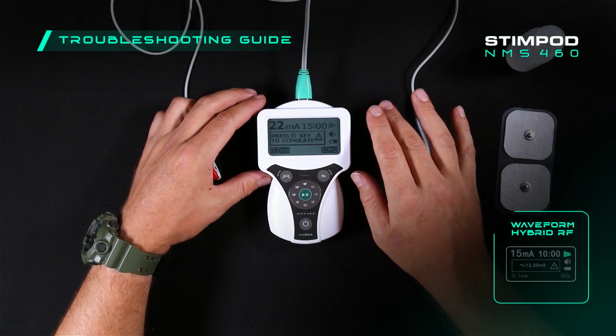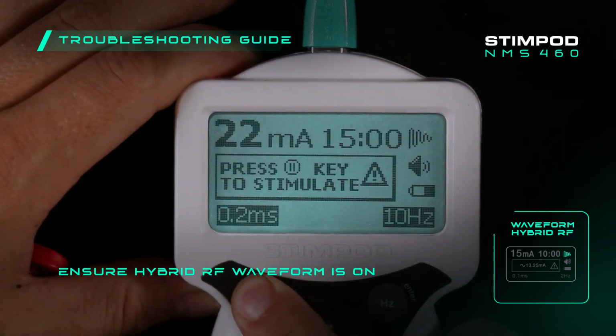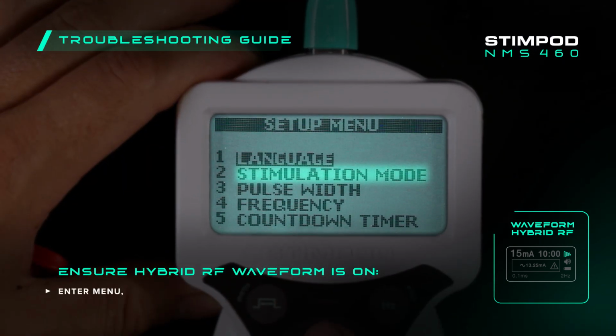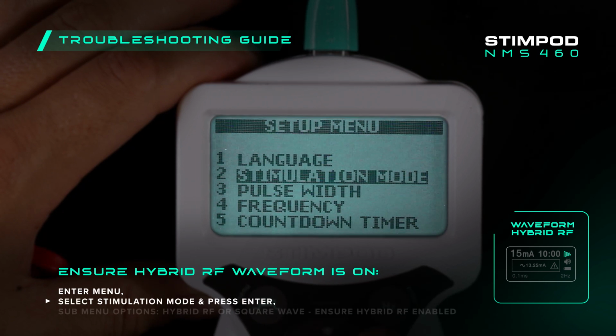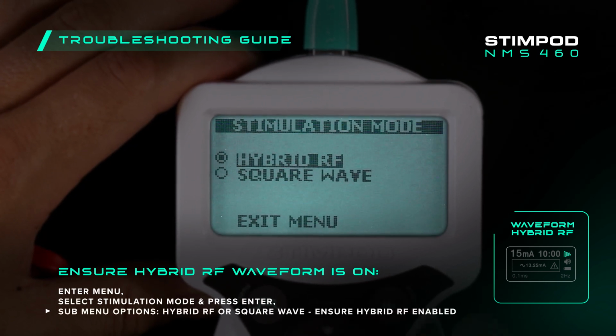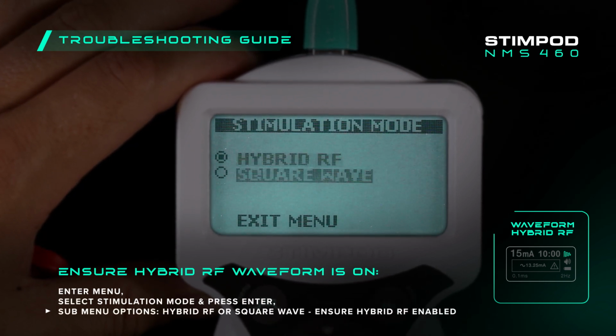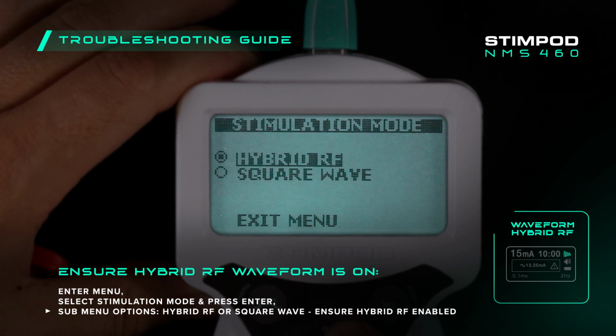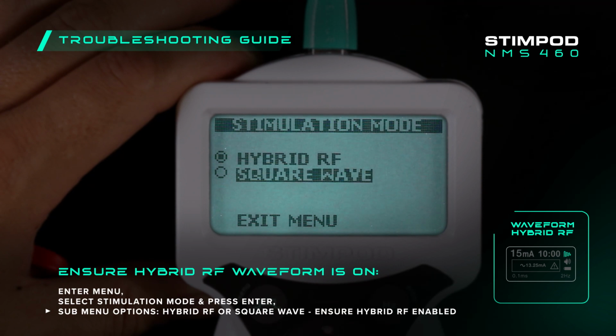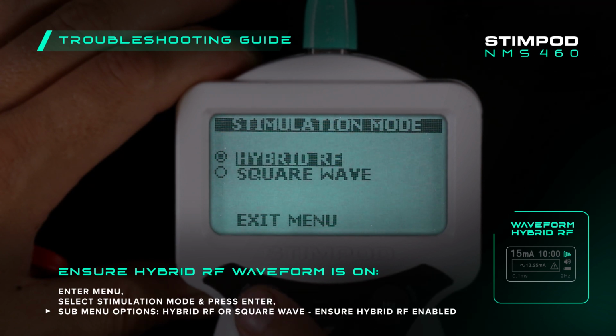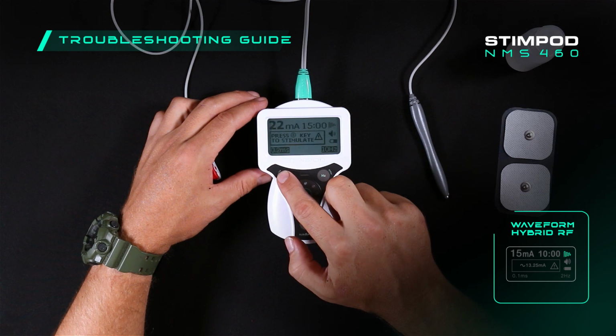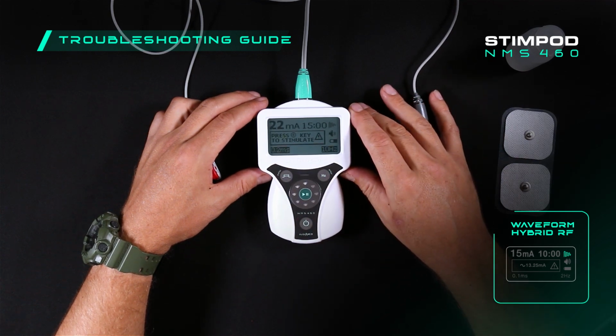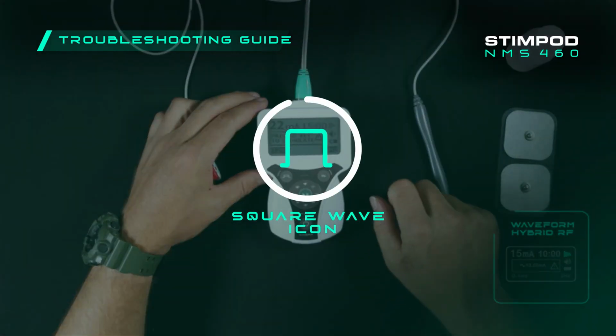To change the wave mode of the Stimpod, press and hold the menu button to open the menu. Use the touch wheel to scroll down to option 2, Stimulation mode, and press enter. On the Stimulation mode submenu, there are two options to choose from. Ensure the hybrid RF waveform option is selected and exit the menu. It's important to ensure that the hybrid RF mode is always selected when treating a patient. If the Stimpod is set to square wave mode, there will be no therapeutic effect.